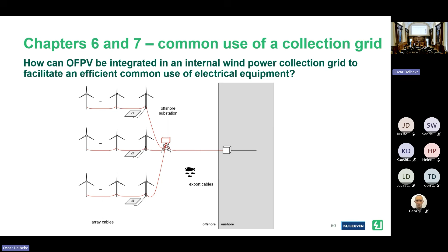To do this, I again had to make use of my characteristic charm and a lot of patience to obtain industrial data that power producers do not really like to share. This is the reason why I blurred the single line diagram, you cannot see the values. The nice thing about this case study is that it is a very modern grid, 15 megawatt turbines and a 66 kilovolt power collection grid.